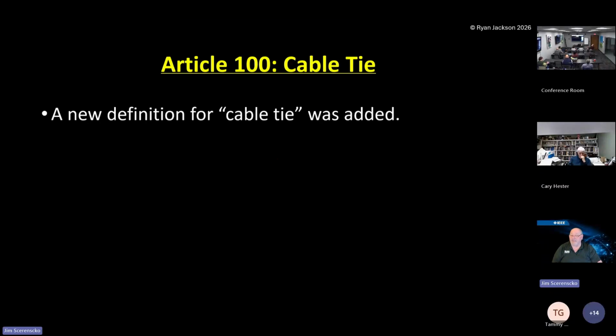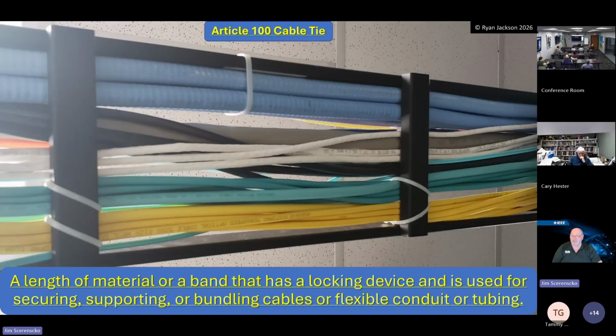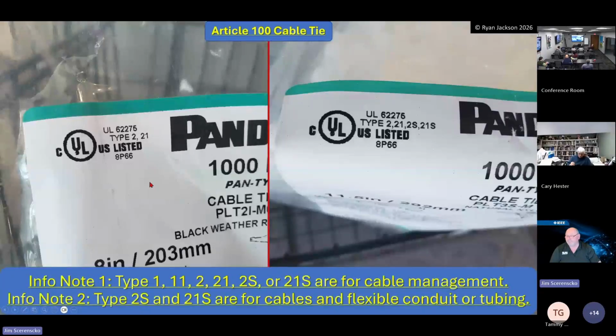Believe it or not, cable ties have a definition now, okay? A definition for a cable tie: a length of material or a band that has a locking device and is used for securing, supporting, or bundling cables or flexible conduit or tubing. Okay, and of course, they're listed, cable ties in most states, not in this one, not in Oregon, but in Atlanta and Georgia, yes, you must use a cable tie that is listed to support, okay?